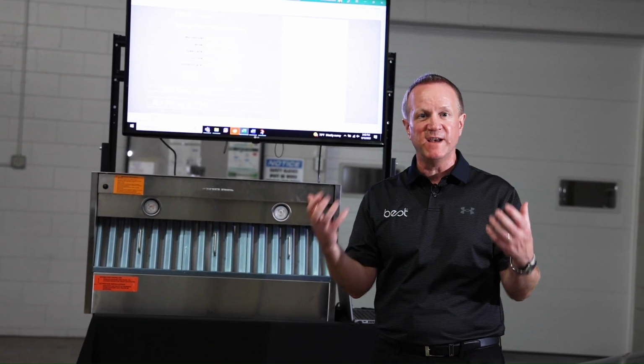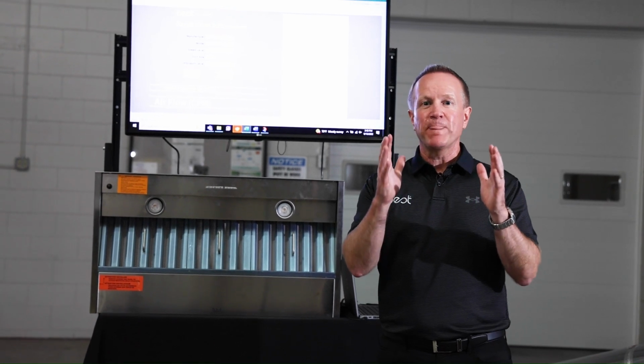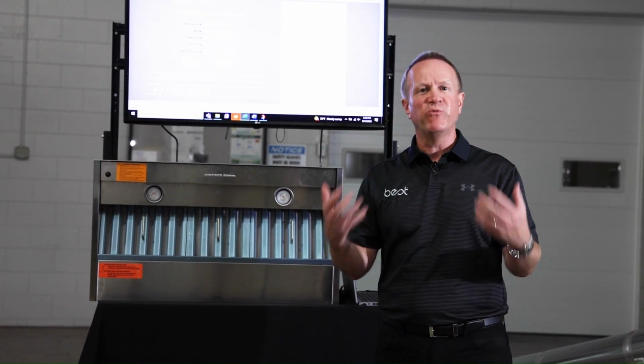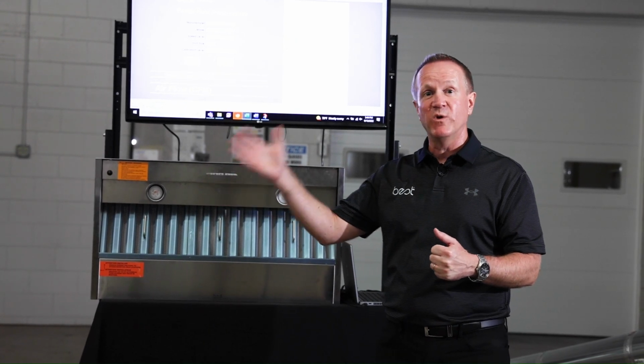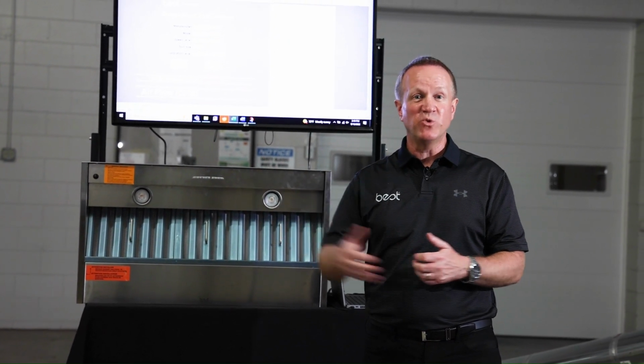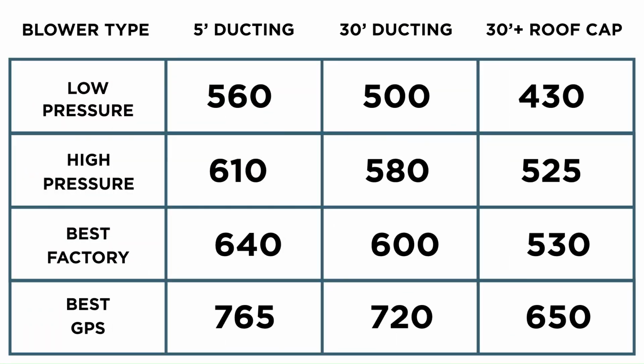But what I can tell you is you take a competitive hood, it's going to perform very similar to what you saw. The high pressure blower in the non-best hood was 525 CFM at full installation. The best hood calibrated was 650 CFM. Now what does that mean? That means you're going to be able to run your hood on low and medium a lot more often than on medium, high, or burst, because not only does the IQ calibrate at that burst speed, that really, really high speed, it calibrates at low, medium, and high as well. So you're getting really strong odor and smoke removal on low, on medium, and on high.